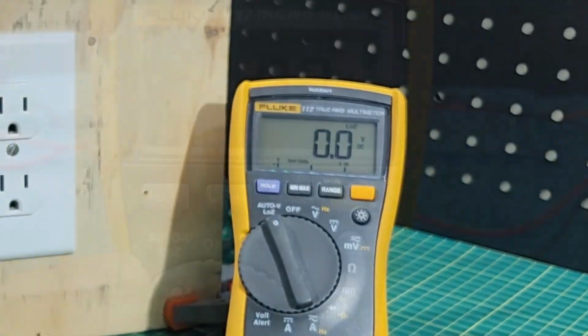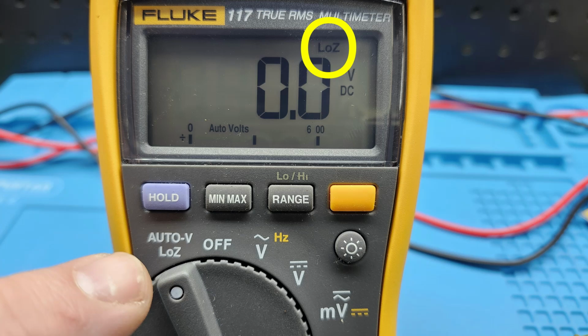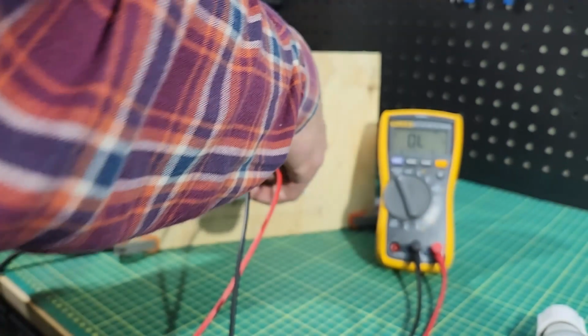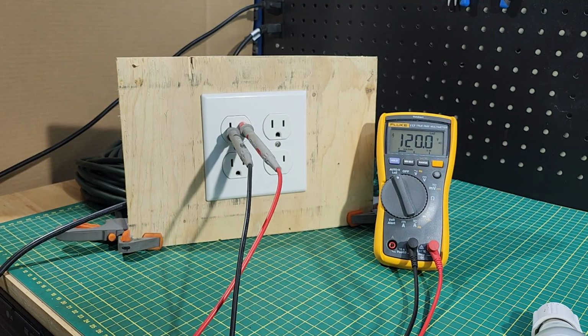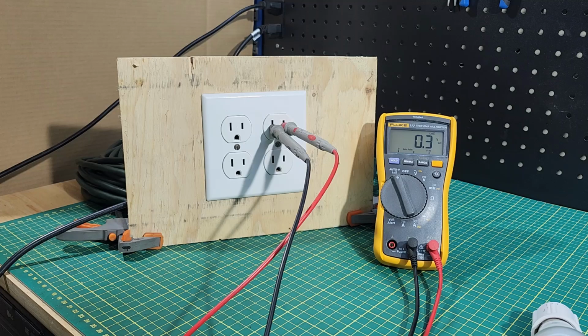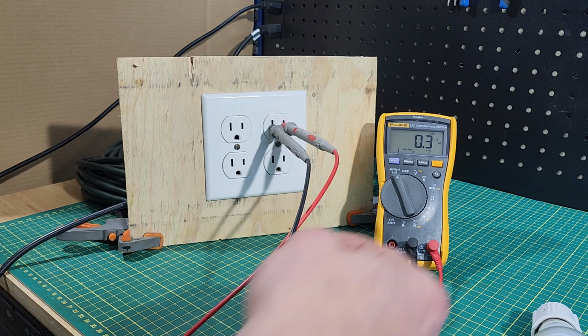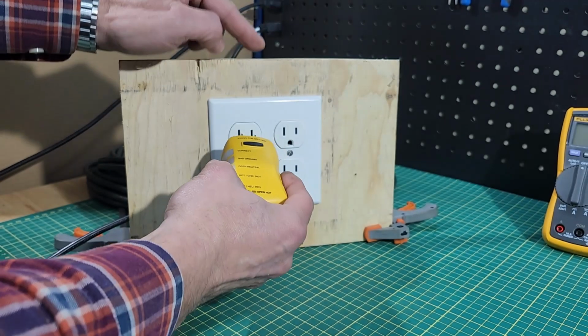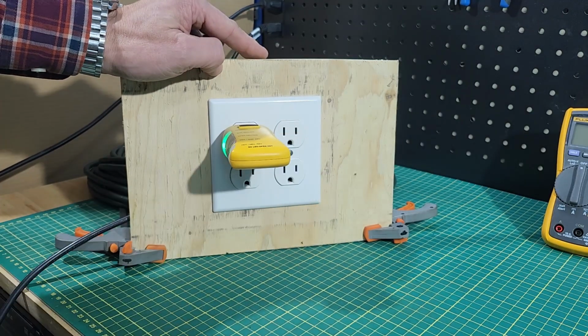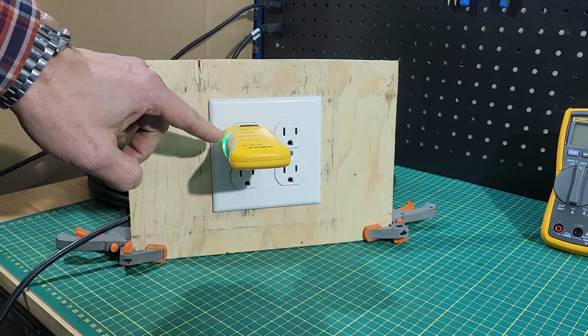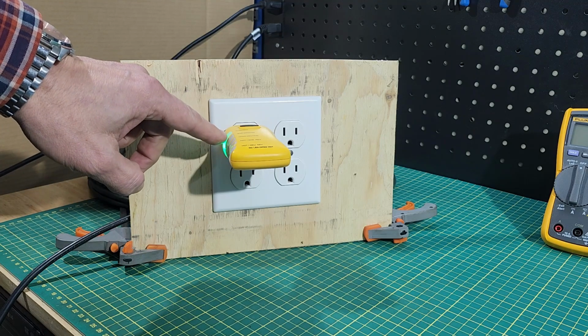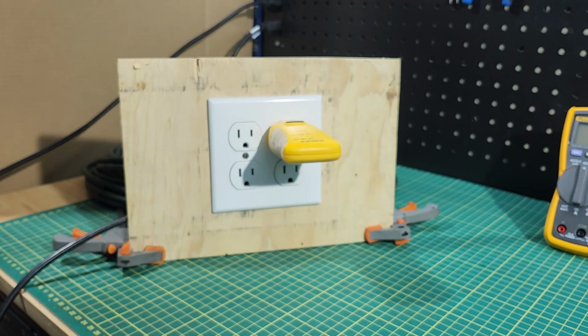I switch the selector to low Z function, low internal impedance. When I plug it into the first outlet, it shows once again 120 volts AC. Leads into the second outlet, and this time we have only 0.3 volts AC. An outlet tester indicates in the first outlet that everything is fine and dandy - green light. The tester shows nothing in the second outlet.